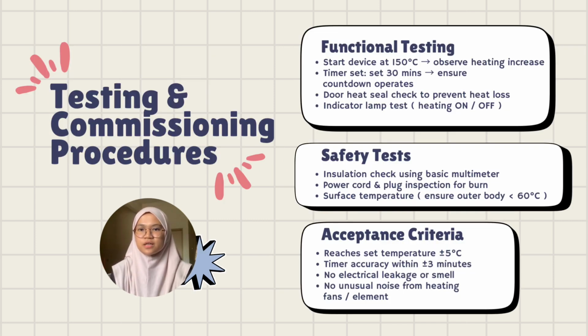Next, functional tests are performed by setting the temperature and timer to ensure proper operation. Safety checks confirm no electrical leakage, no unusual smells, and that the outer surface stays below 60 degrees Celsius. The sterilizer is accepted once it passes all functional and safety tests and acceptance criteria, ensuring it is ready for safe use in the clinic.